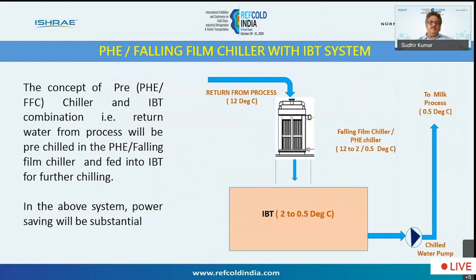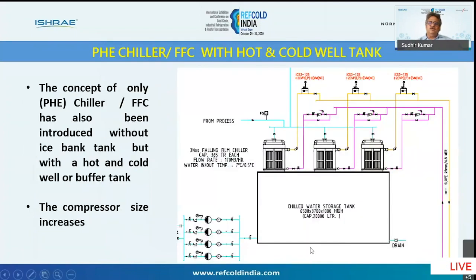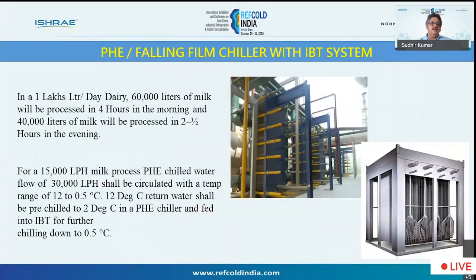And the next concept which we were talking about is using only a PHE with a small tank instead of using an IBT. You can use a falling film chiller with the IBT system, and also another system is without IBT, just have a falling film chiller or a PHE and then collect the water in a tank and use this water for your process. The most energy efficient system will be this one, because it operates at -2 evaporation, and by operating at -2 evaporation, your power saving is definitely better than an ice bank tank system. I have made some small calculation. Say for example, if it is a 1 lakh liter dairy, 60,000 liters of milk will come in the morning and 40,000 comes in the evening.